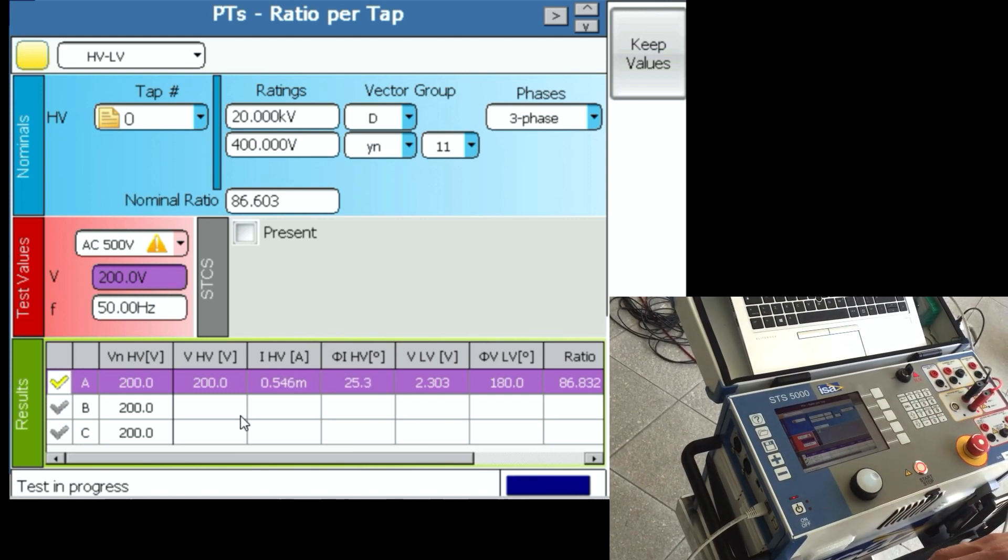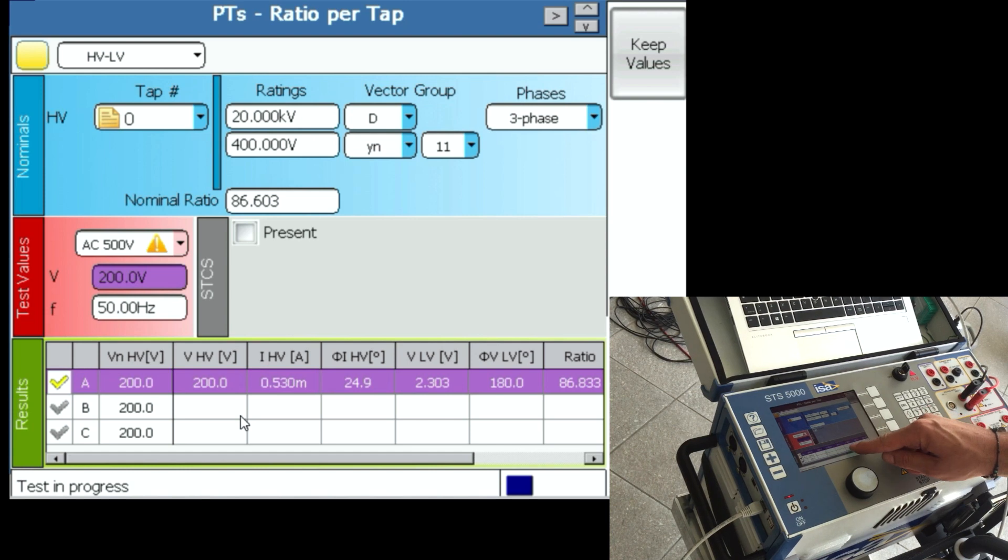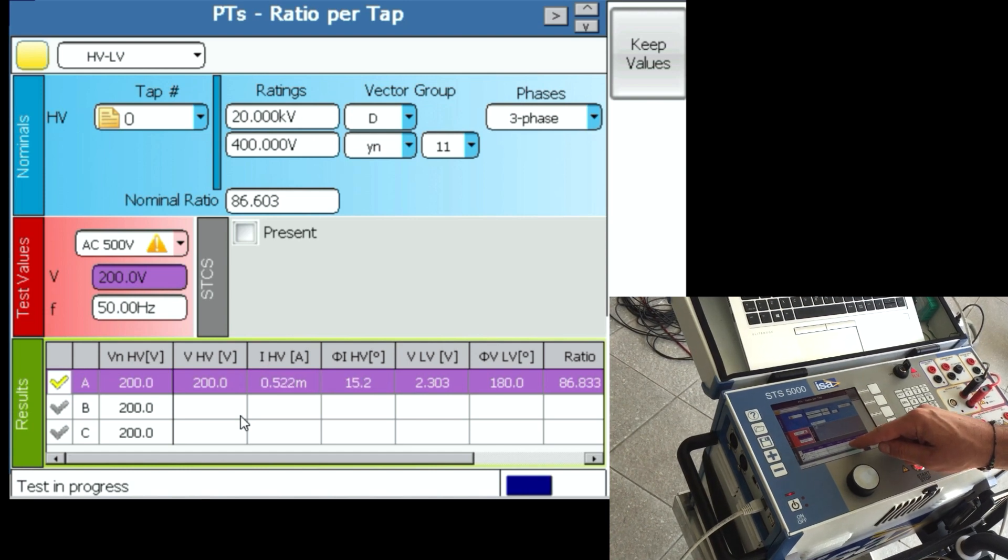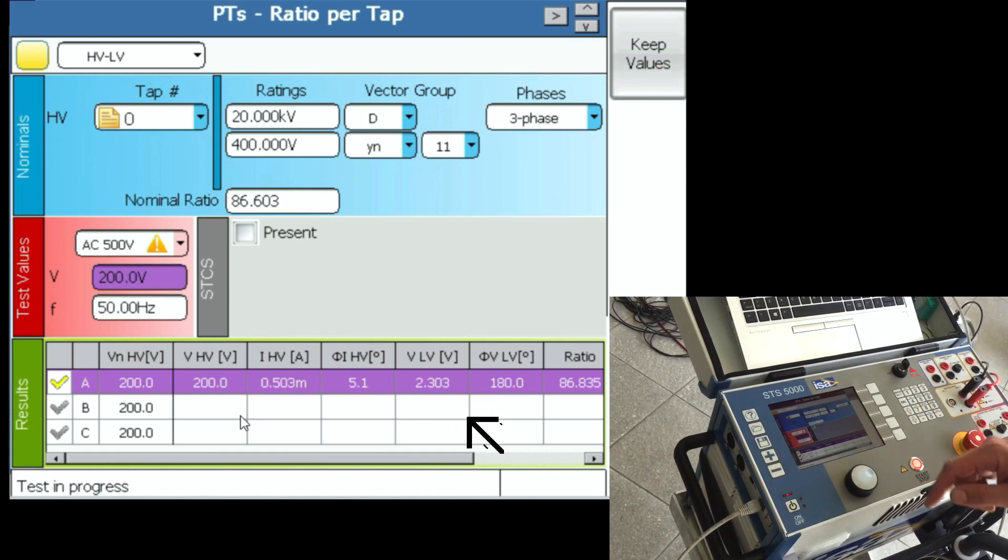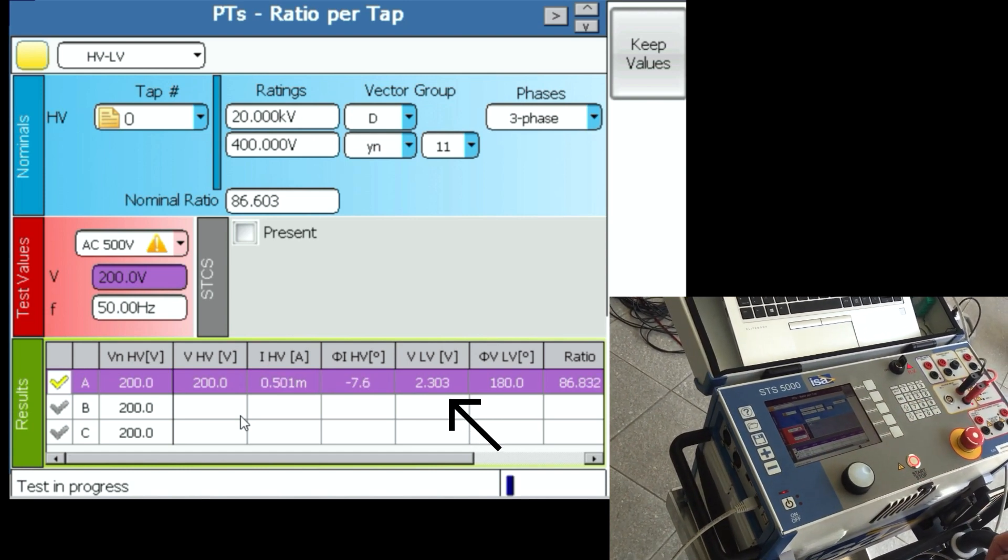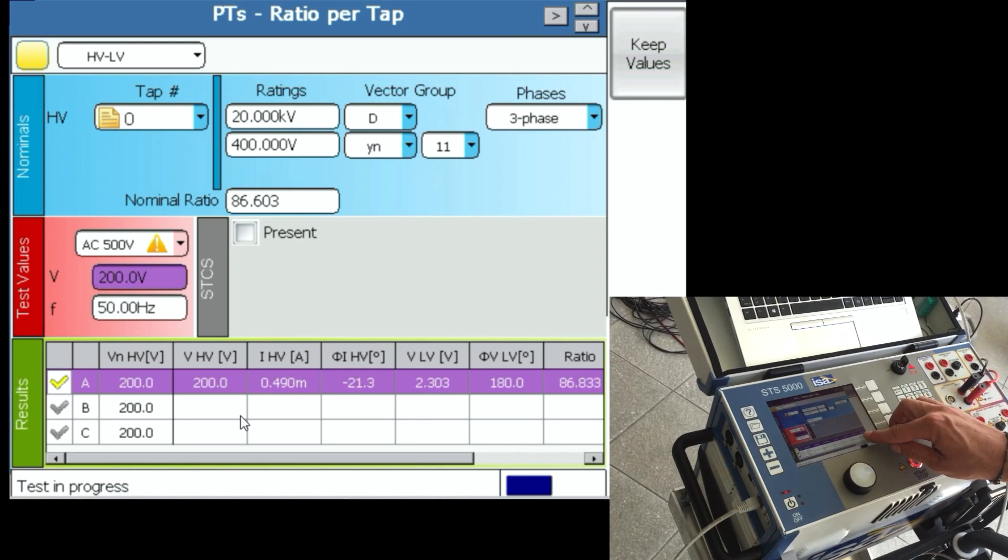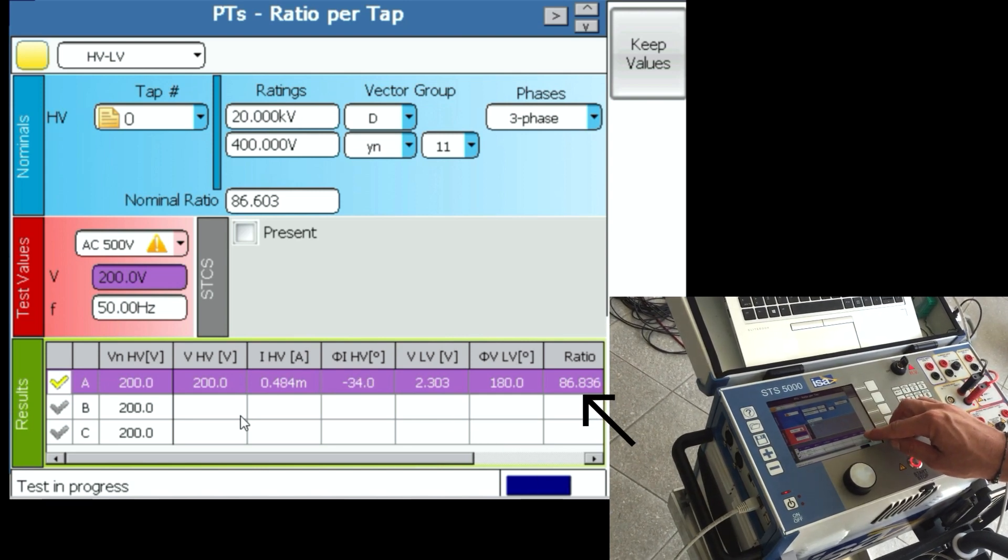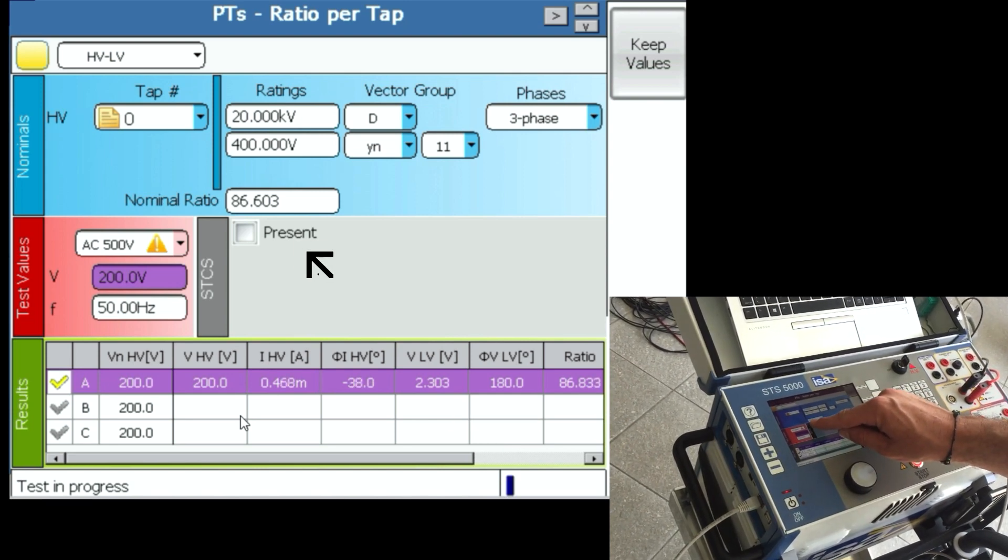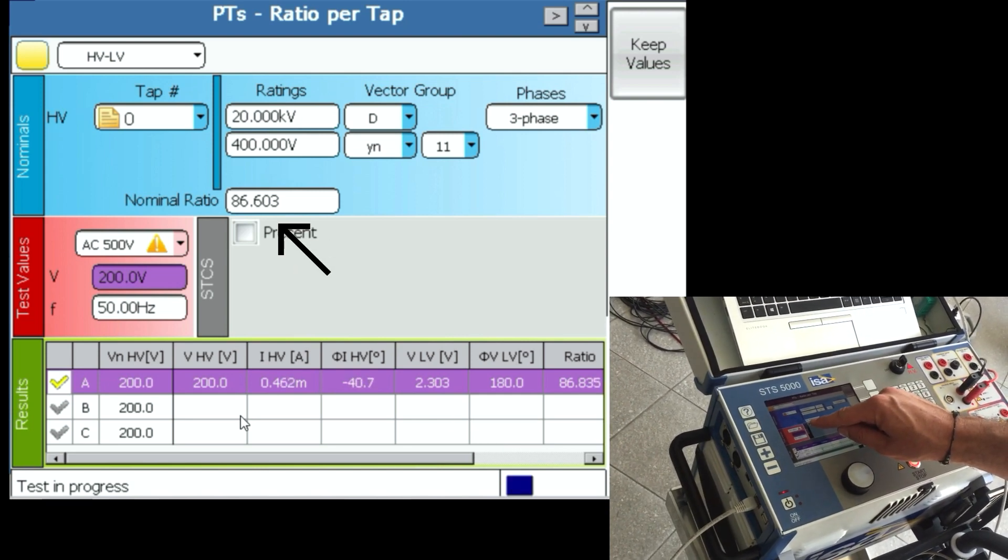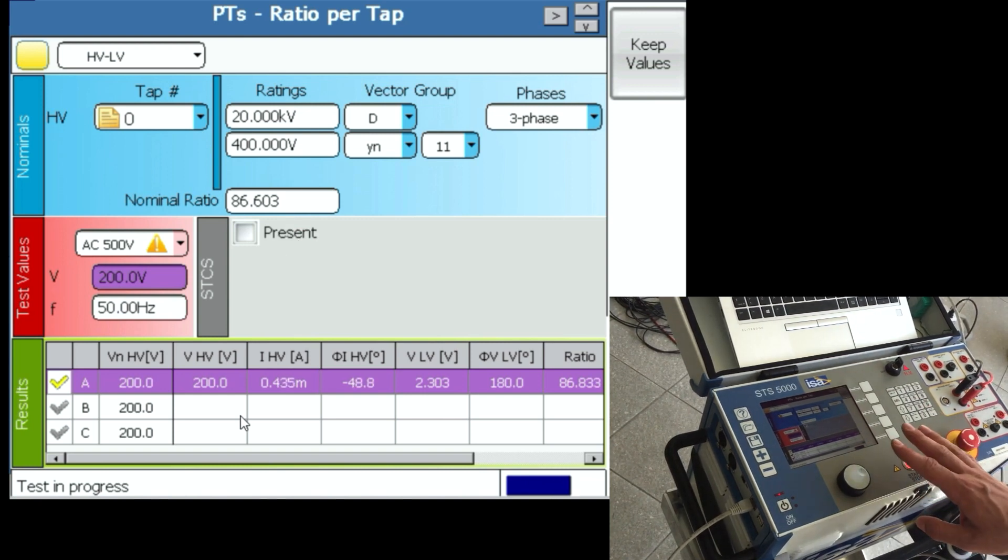Phase shift and then the voltage on the secondary side: 200 on the primary is 2.3 on the secondary side, which gives us the ratio of 86.83. Our nominal is 86.60.